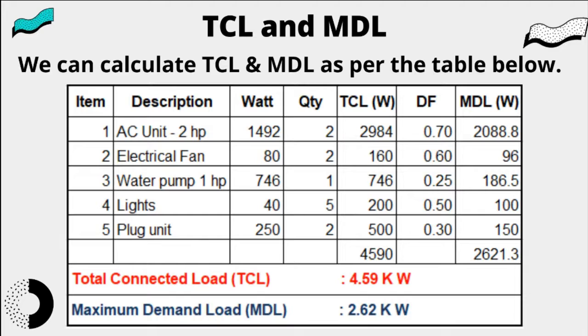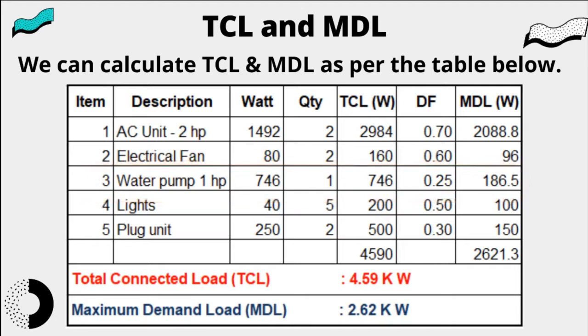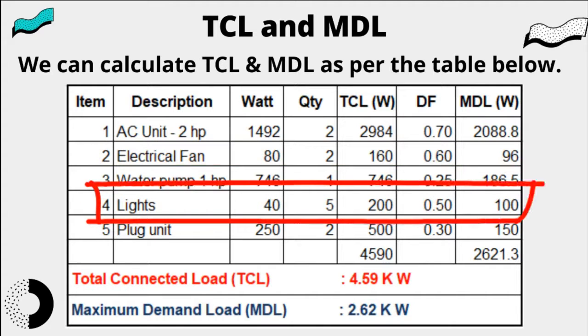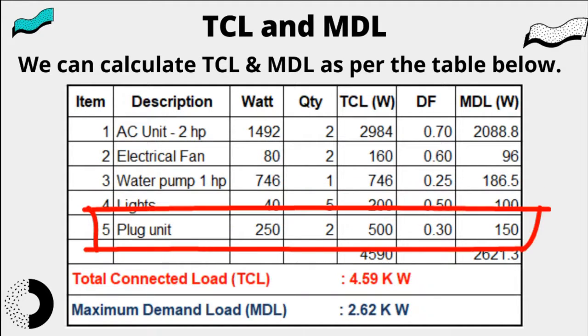Although the TCL is 746 watts, the MDL of the water pump is 186.5 watts because the DF is 0.25. The total load of the five lights is 200 watts and the MDL is 100 watts as the DF is 0.50. The TCL of the two plug units is 500 watts but the DF is only 0.30, so the MDL is 150 watts.